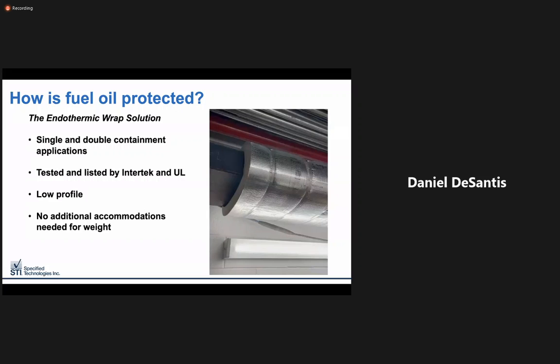Testing for single and double containment fuel oil systems has been conducted in third-party labs like UL and Intertek. Endothermic wrap is only 1/2 an inch thick per layer. This saves space for the shaft within a shaft applications. No additional weight or reinforcement is needed to accommodate the weight of E-wrap. It is a standalone shaft alternative that fits existing hangers and standoffs used by pipe fitters around the country.